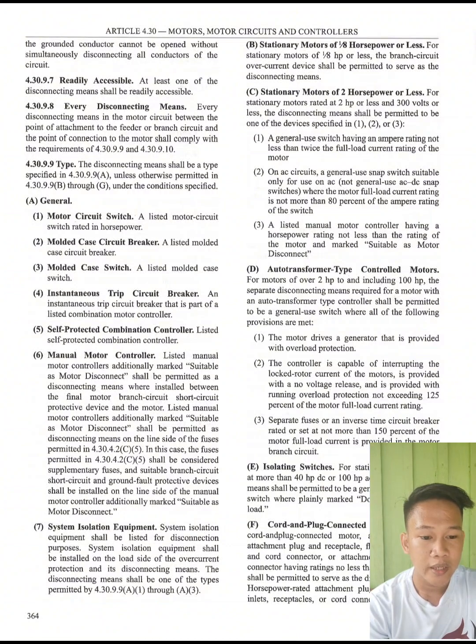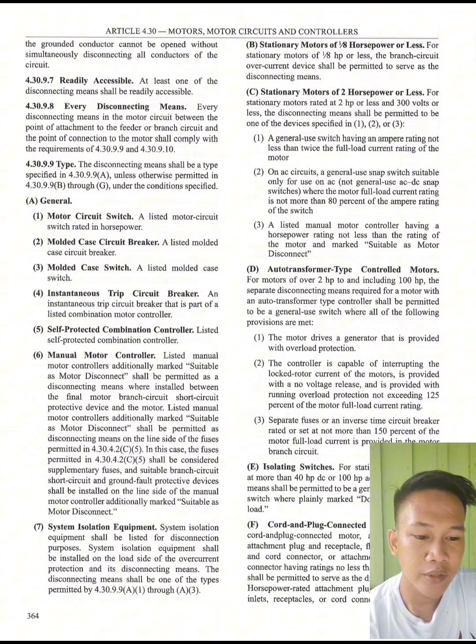So, letter D. Next is letter D, autotransformer-type controlled motors. For motors over 2 horsepower up to and including 100 horsepower, the separate disconnecting means required for a motor with an autotransformer-type controller shall be permitted to be a general-use switch where all of the following provisions are met. First, the motor drives a generator that is provided with overload protection. Second, the controller is capable of interrupting the locked-rotor current of the motor, is provided with no-voltage release, and is provided with running overload protection not exceeding 125 percent of the motor full-load current rating. Third, separate fuses or an inverse time circuit breaker rated or set at not more than 150 percent of the motor full-load current is provided in the motor branch circuit.